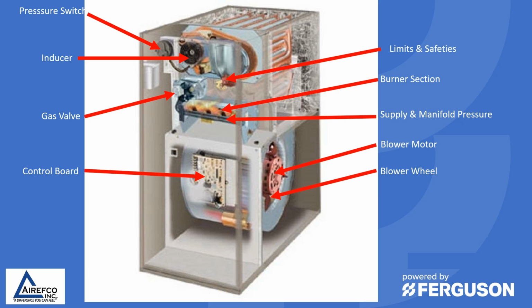The blower motor needs to spin freely, needs to be drawing the proper amp draw, and it needs to be producing the CFM that is required for the furnace. So double checking the blower motor, whether it's a regular PSC motor or an ECM motor, for proper operation is part of a furnace tune-up.